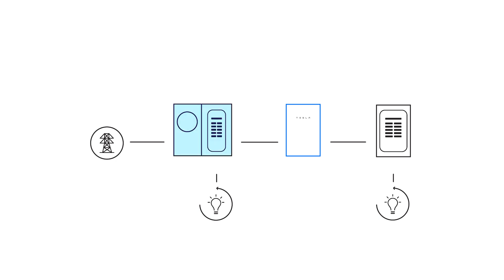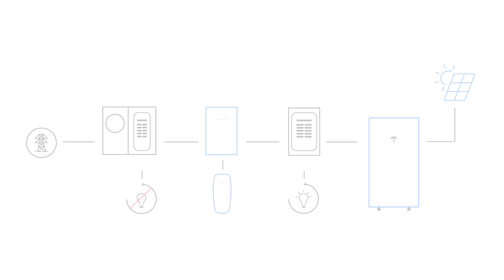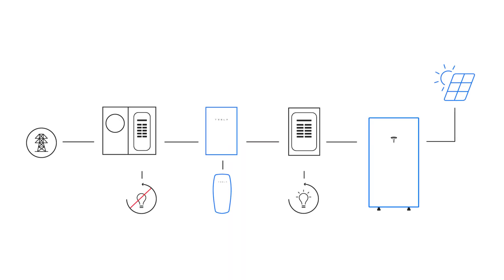Any critical loads in the main panel must be relocated to the backup panel. Any loads that do not need to be powered during an outage can remain in this panel, while still being fed by solar and Powerwall during normal grid-connected operation.